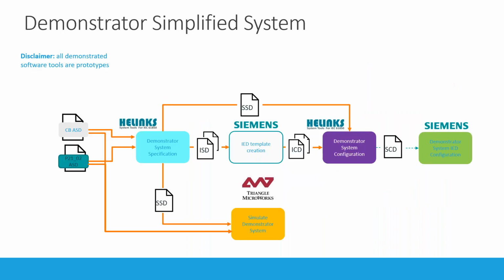The process we will demonstrate is exactly the same as the one explained in the slides before: taking the profile from the top of the process, taking both application templates, building a system specification inside the Helinks tools, building the individual IED specifications, then handing them over to Siemens to create the ICD files, and afterwards combining both inside a system configuration, which can then be used to finalize the configuration of the IED. Triangle will demonstrate how an individual application can be simulated and tested so it can be validated and used inside the remaining steps of the process.